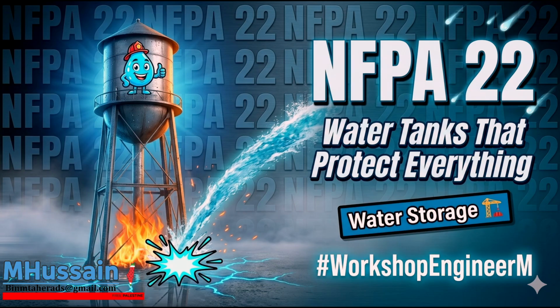Even the fire retardant resins will lose their structural integrity rapidly when exposed to the high heat flux of a room fire. If the ambient heat softens the resin, the tank will burst and you instantly lose your water supply. The ordinary hazard group 2 requirement dictates a specific heavy density of water spray to suppress the room fire and cool the tank surface before it reaches its critical failure temperature.